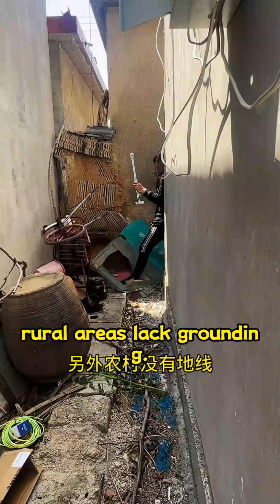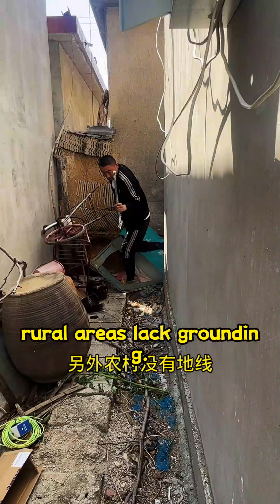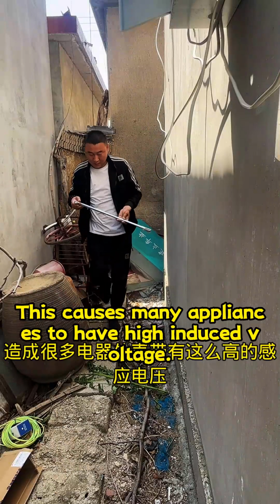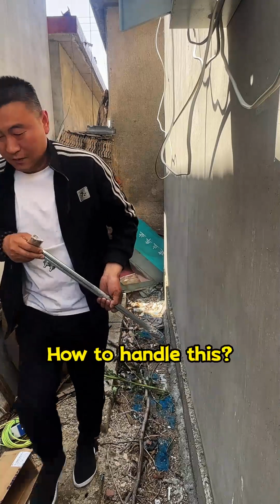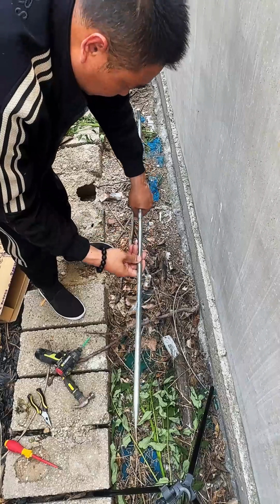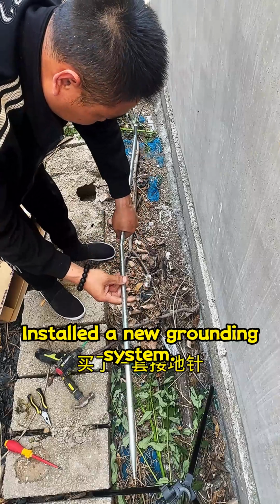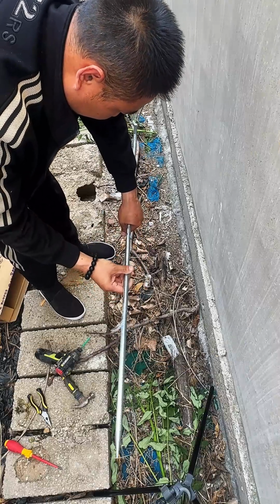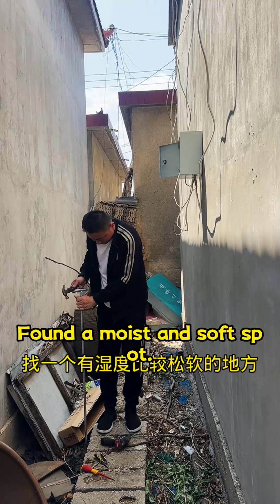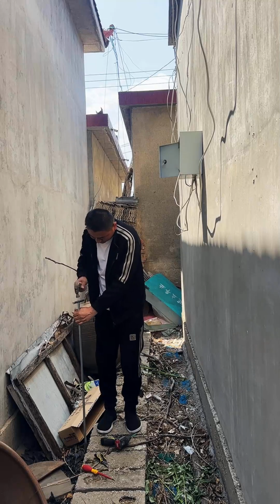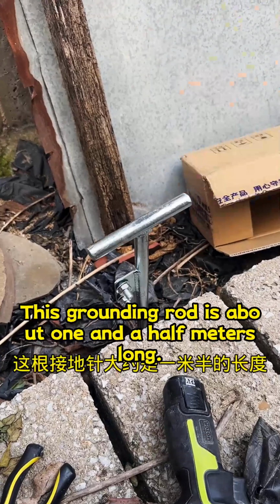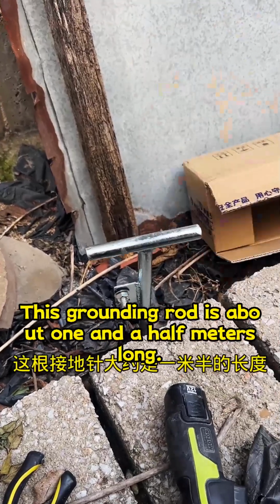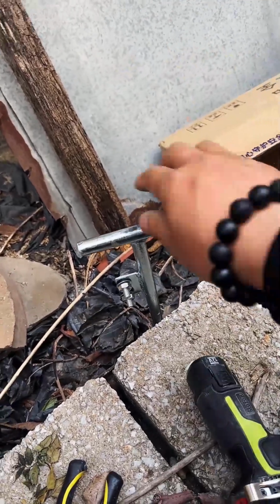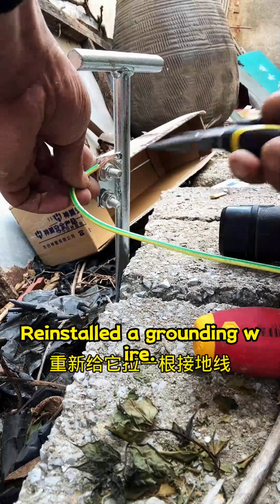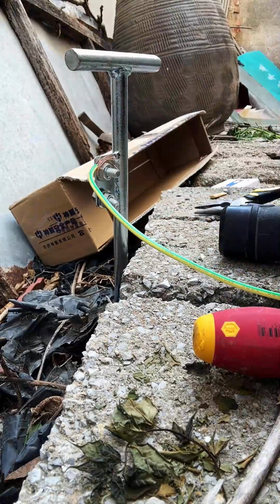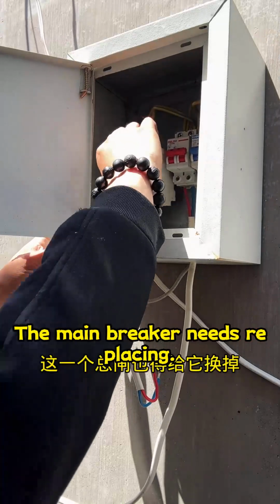Additionally, rural areas lack grounding. This causes many appliances to have high induced voltage. How to handle this? Bought a grounding rod. Installed a new grounding system. Found a moist and soft spot. This grounding rod is about 1.5 meters long. Reinstalled a grounding wire. The main breaker needs replacing.